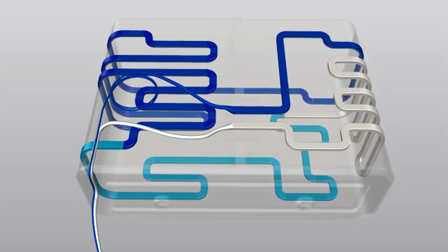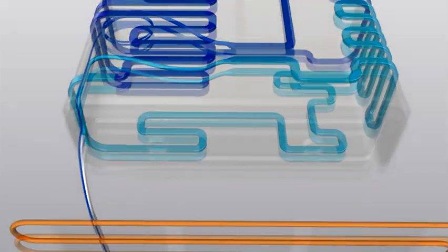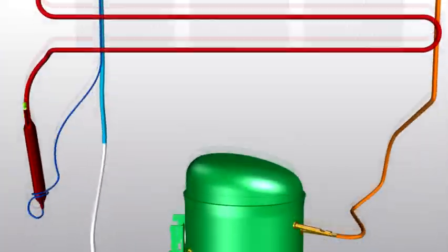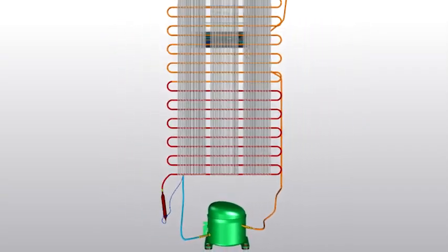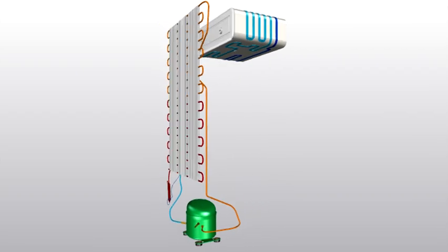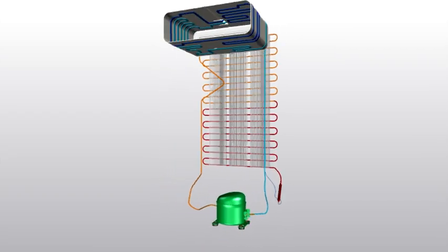As an inclined accumulator is connected at the end of evaporator, only vapor refrigerant enters the suction line. Due to the heat exchanger effect while returning, the vapor refrigerant gets superheated and enters the compressor. The cycle thus continues as long as the compressor is fed the electrical power.